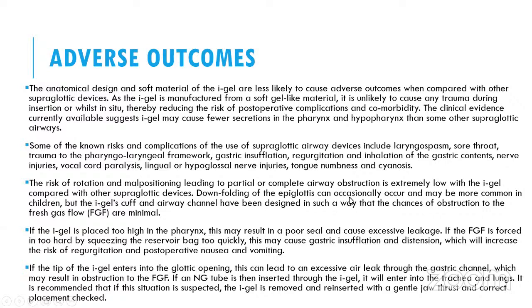Downfolding of the epiglottis can occasionally occur and may be more common in children, but the I-gel cuff and airway channel have been designed in such a way that the chances of obstruction to the fresh gas flow are minimal. If the I-gel is placed too high in the pharynx, this may result in a poor seal and excessive leakage. If the fresh gas flow is forced too hard by squeezing the reservoir bag too quickly, this may cause gastric insufflation and distension, which will increase the risk of regurgitation, postoperative nausea, and vomiting.